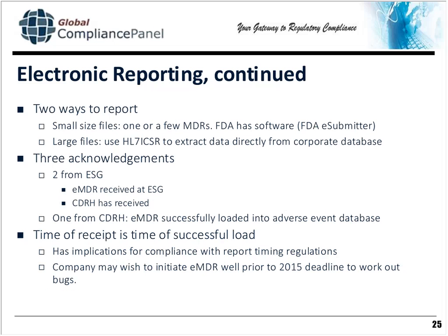There are two ways to report. For small-size files, one or a few MDRs, FDA e-submitter, which FDA has and which you can use, is the way you'll do it. For large files, you can use this HL7 ICSR to extract data directly from a corporate database. Then you'll get an acknowledgement. Two of them will be from that electronic systems gateway. First of all, you'll receive an acknowledgement that the eMDR was received at ESG. Then there'll be another one that ESG has passed it to CDRH. Finally, you'll get one from CDRH, that is the Center for Devices and Radiological Health, that the MDR was successfully loaded into their adverse events database.